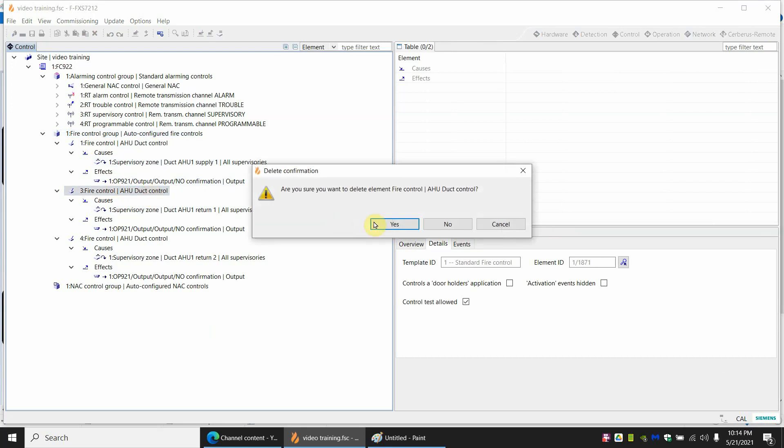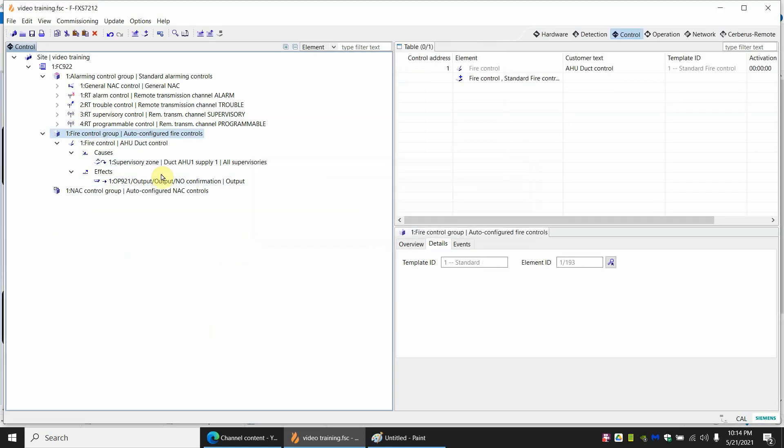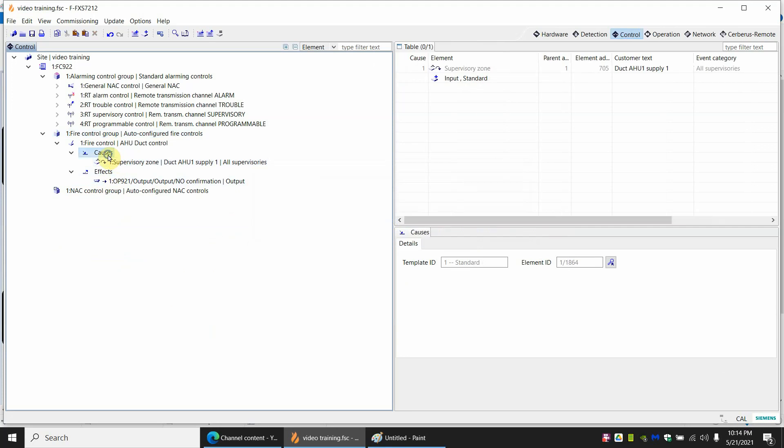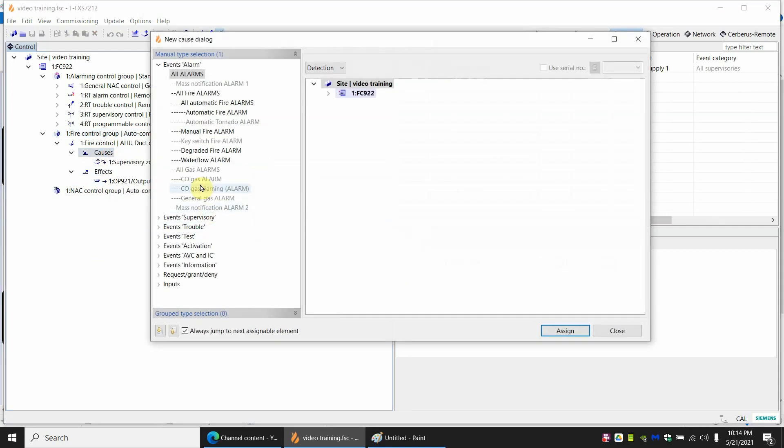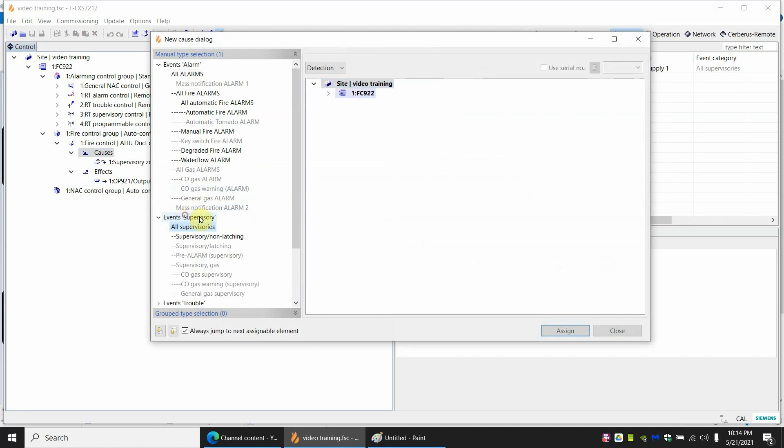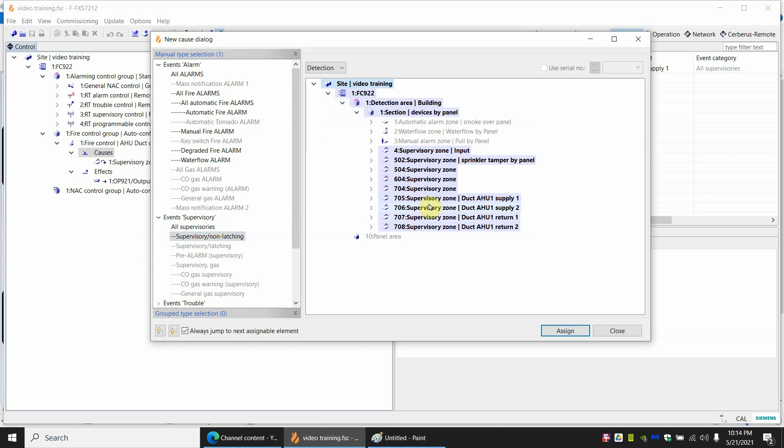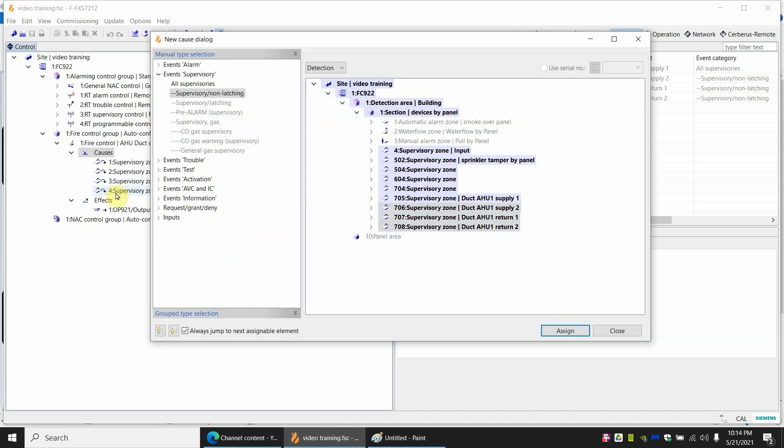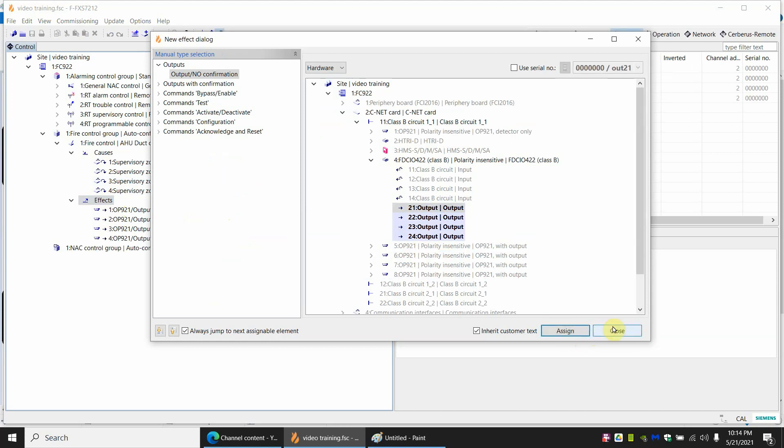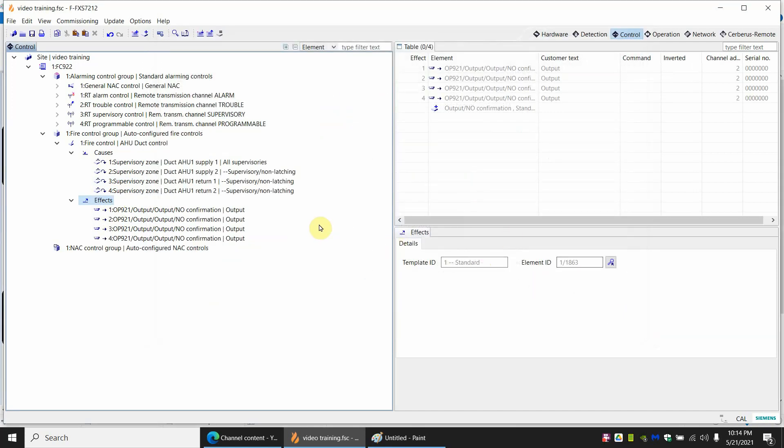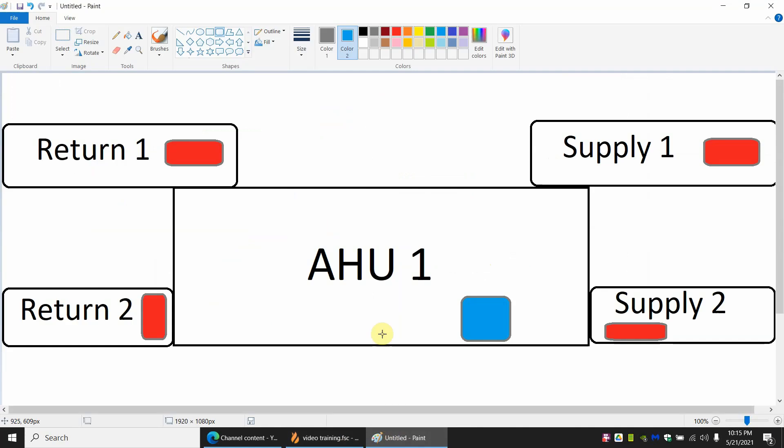Again I said this was an OR. So if anything here in the causes goes off, it's going to trigger the effects. So in the causes, if we added all the duct detectors here for that air handler unit. Again it's supervisory. We said two, three, and four. Okay, all four of them are in there. And the effects, we're going to pick all of them again. Now this control is saying, if any one of these four go off, we're going to trigger all four of the relays. And to go back to the crude picture, we're saying, hey, if return two goes off, all four of these relays trip. If return one goes off, all four of these relays trip.